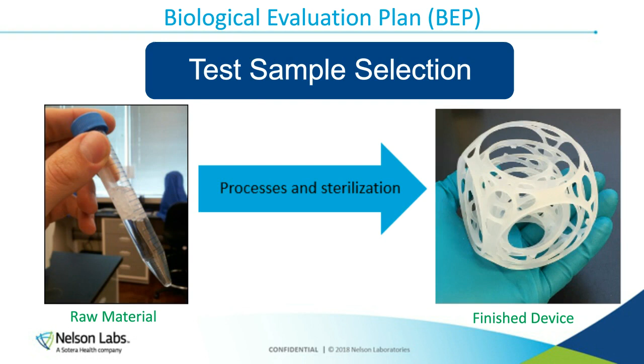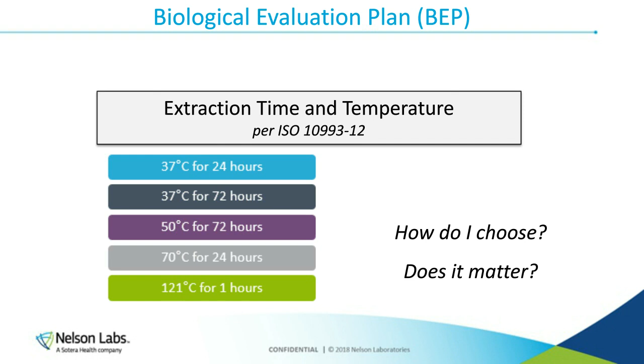I have this extra slide in here. I just wanted to go over it again a couple of times with you guys. Okay, here we go, the extraction time and temperature. This is also important because the FDA has specifically asked for certain parameters based on the contact duration of the device with the patient. Typically this first one here is for cytotoxicity only. Now, this is all listed in 10993 Part 12.